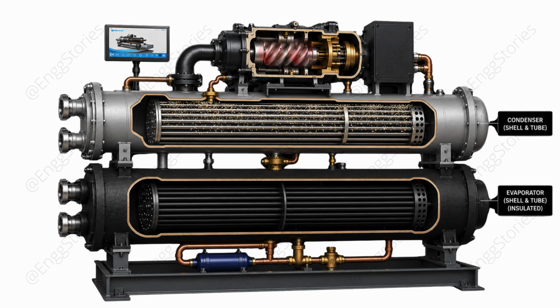Here, it transfers its heat to the condenser water flowing through the tubes. As the refrigerant loses heat, it condenses into a high-pressure liquid, while the condenser water carries the heat to the cooling tower. After that, the high-pressure liquid refrigerant passes through the expansion valve. As it passes through the valve, its pressure drops suddenly, which also causes its temperature to drop. It leaves the expansion valve as a low-pressure, low-temperature liquid and enters the evaporator.